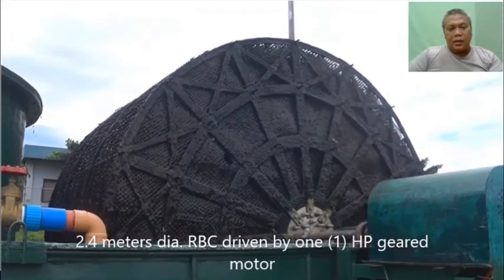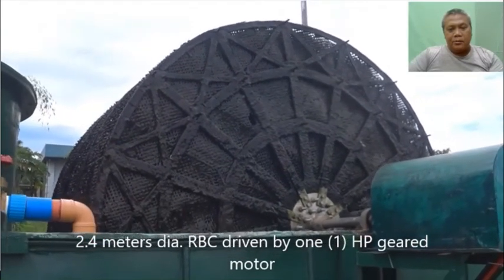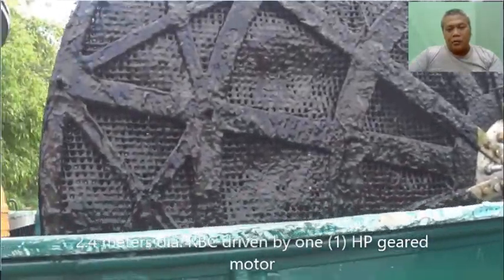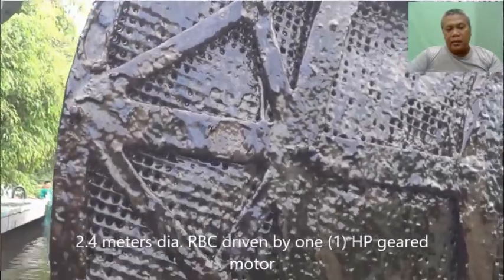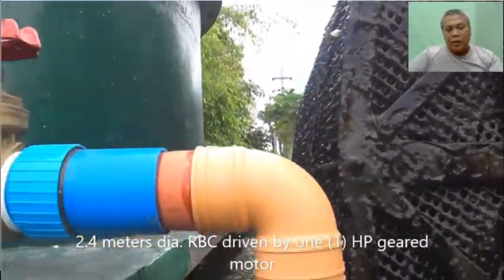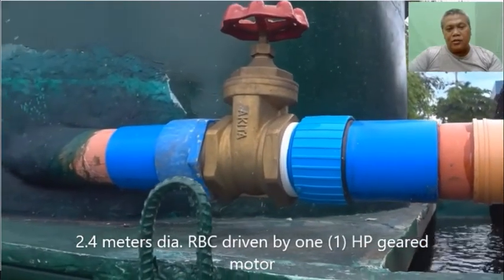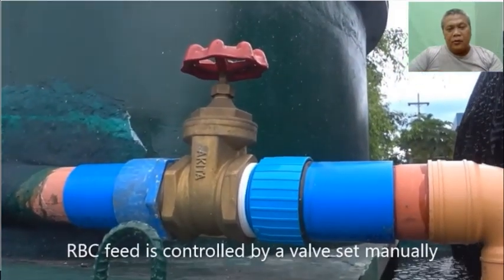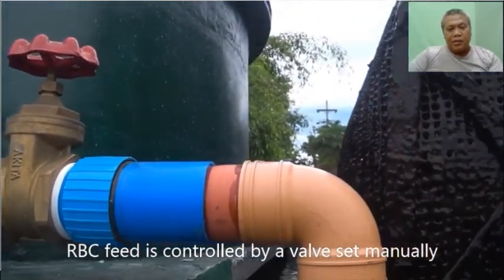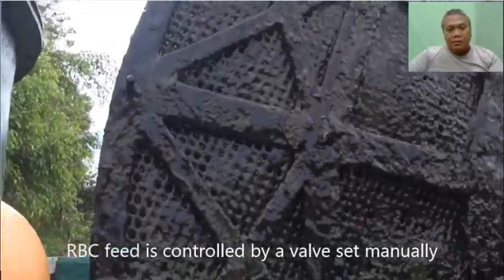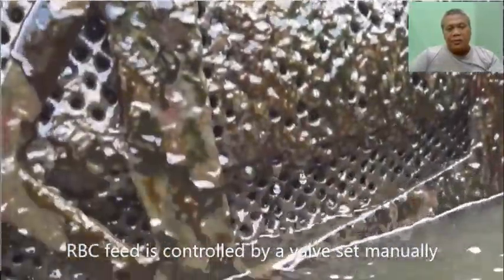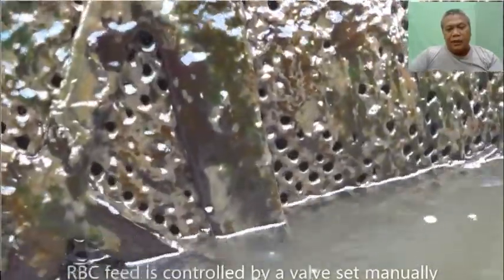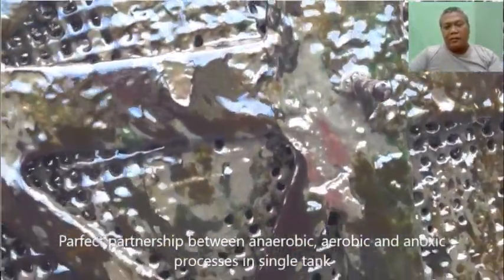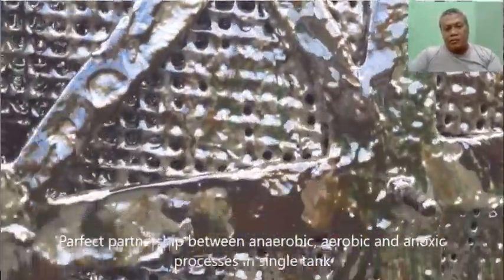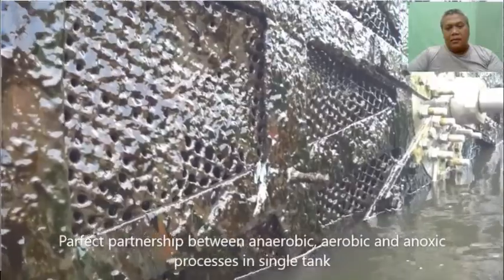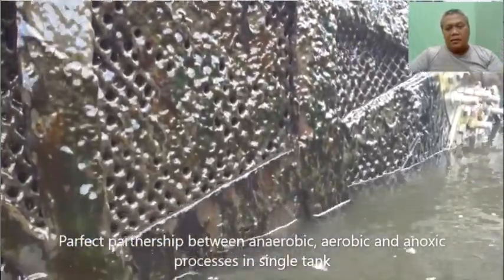This is rotating at 1 RPM. This is the other side. It is driven by a 1 horsepower motor, and the diameter is 2.4 meters. This is the valve that controls the inflow of the wastewater going to the RBC. This is manually set. You can see that this RBC biofilm is 5 months old, and it has never been detached, so it is continuously thickening in the media of the RBC.